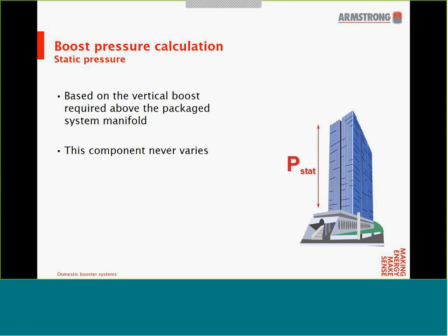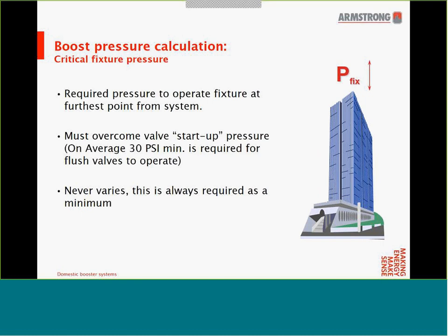After determining the flow, the second step is to determine the boost pressure required. There are five components to calculating the boost pressure. The first is the static pressure, determined by the vertical boost required to bring the water to the top floor — this component doesn't vary. The second component is the pressure required to operate critical fixtures at the furthest point from the booster system. Typically, flush valves are the limiting factor, requiring at least 30 psi to operate. This pressure doesn't vary and is required as a minimum.